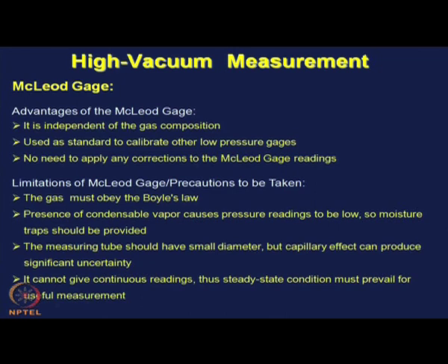The measuring tube or the sealed capillary tube should have a small diameter, but we have to be careful that there should not be any capillary effect, because if the diameter is too small, there can be capillary effect, and the capillary effect can produce significant uncertainty.